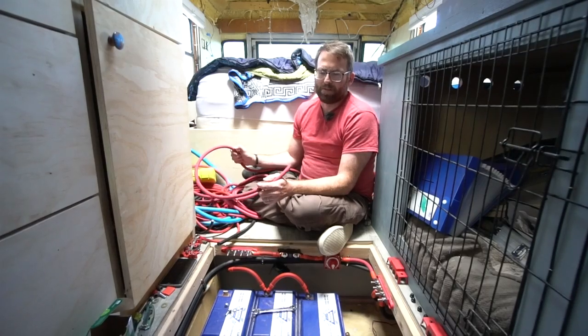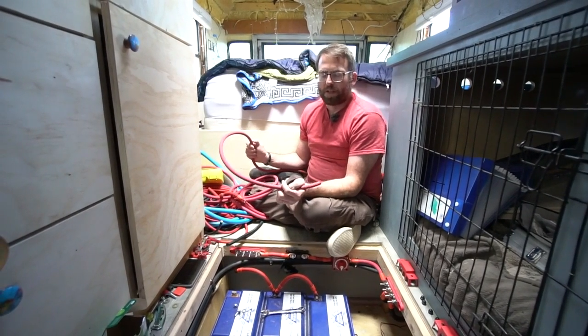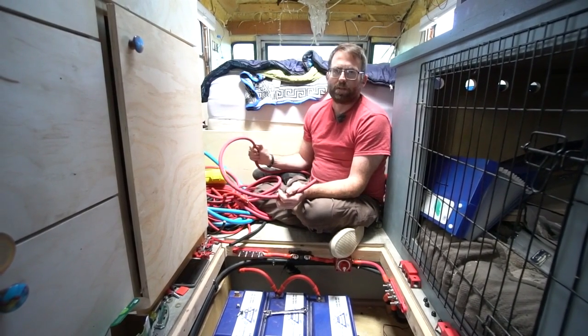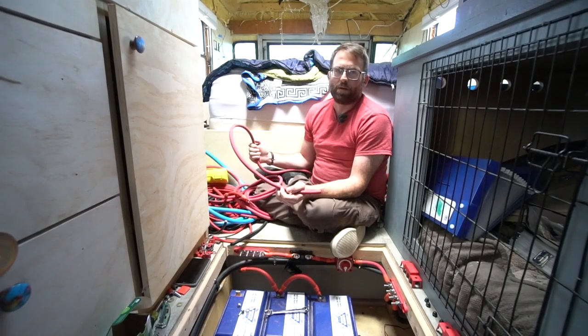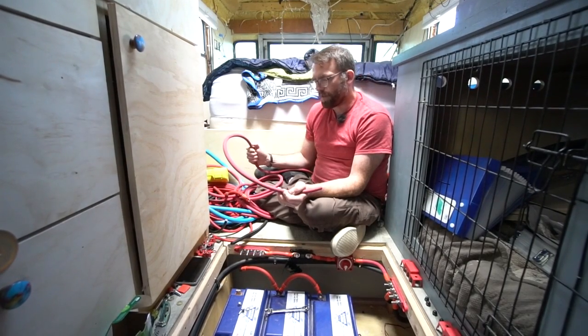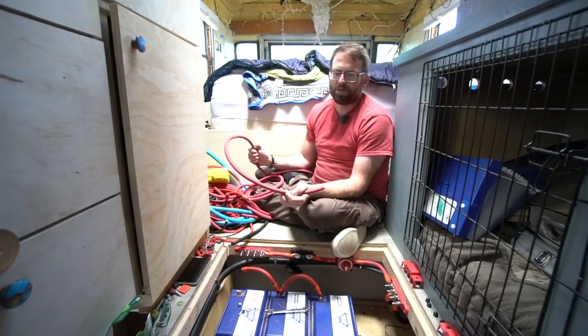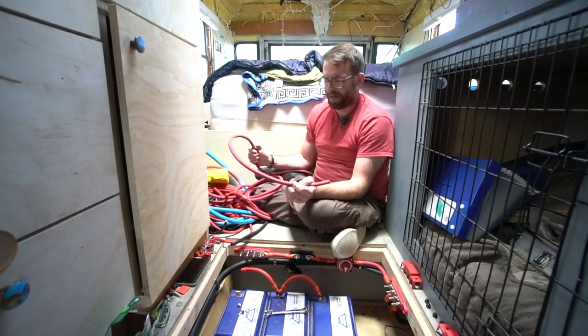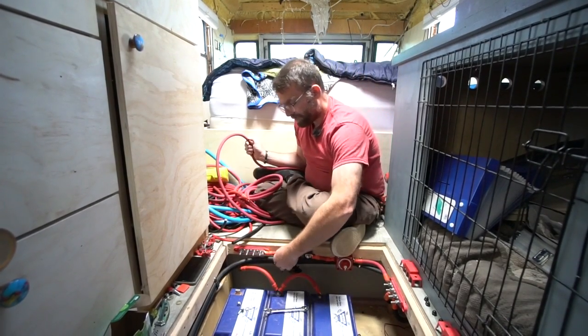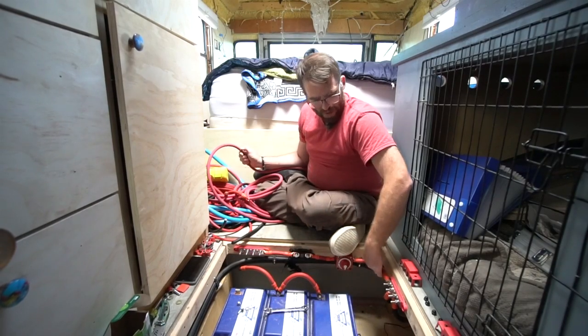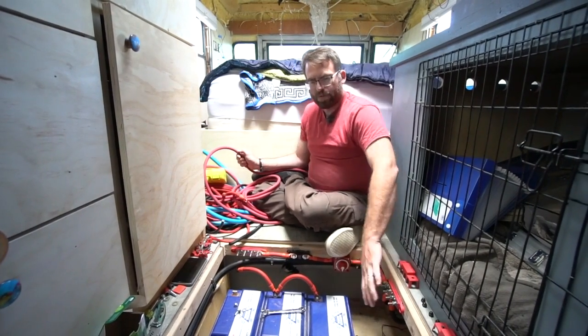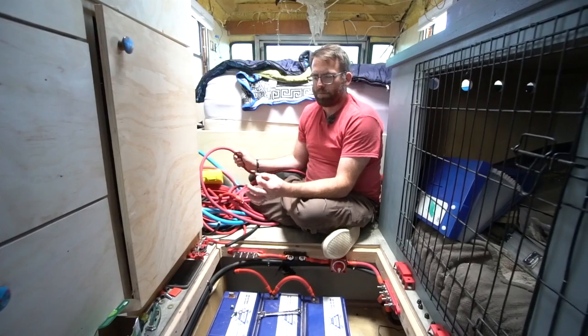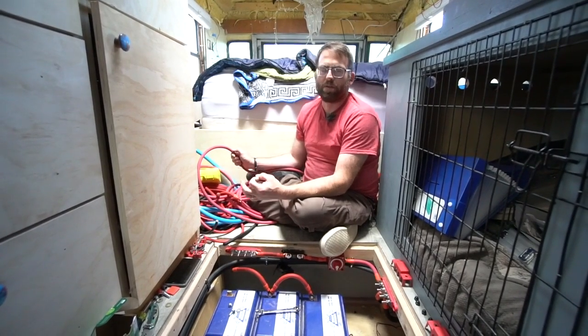That's why we're using at least 2-gauge cable. 4/0-gauge cable may even be necessary, but we're only going to be connecting a 3 kVA inverter to this, so about 3,000 watts at the most. If we had a larger inverter, we would be using 4/0-gauge cable for these main runs back to it as well. They're pretty short right now, but everything's sort of distributed, so we don't need to have some huge single point of failure cabling right now.